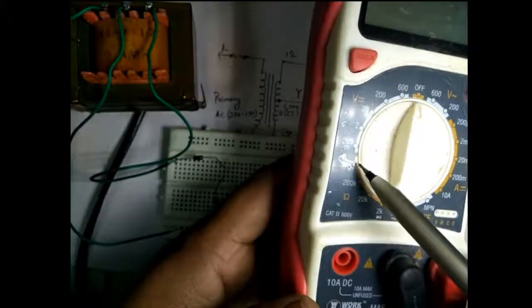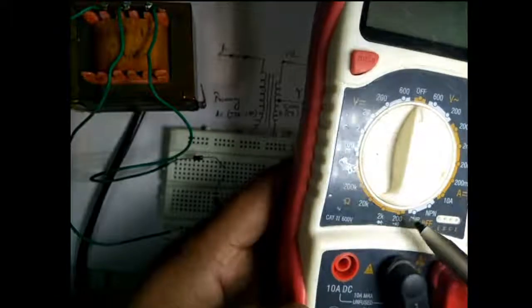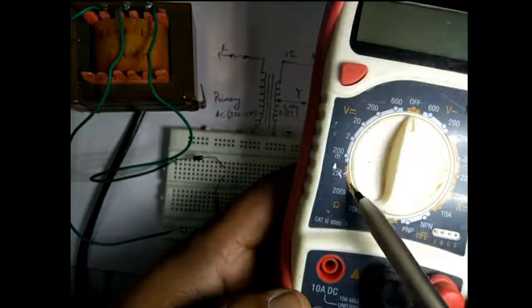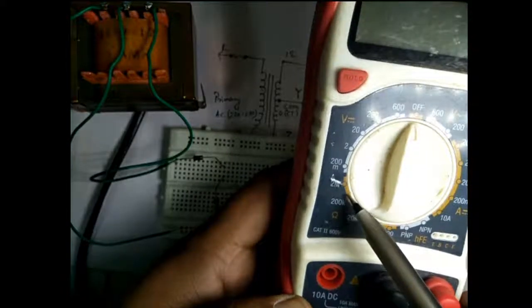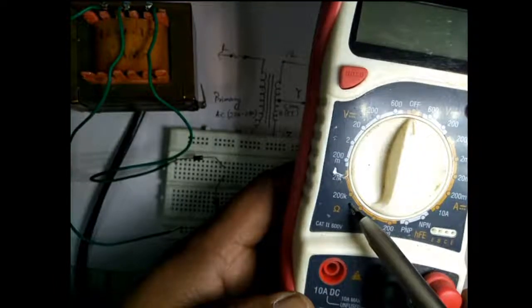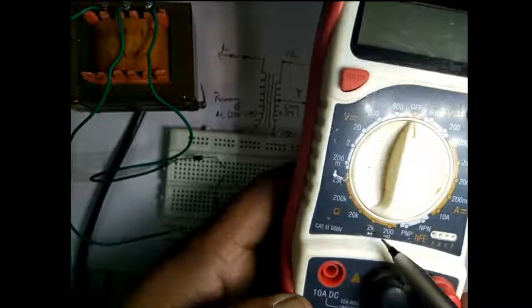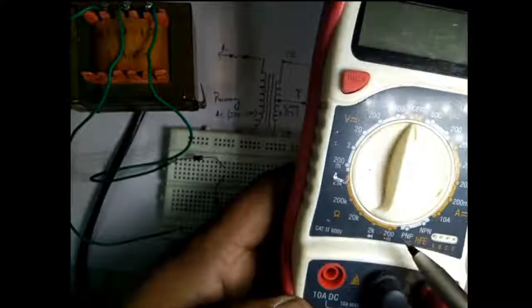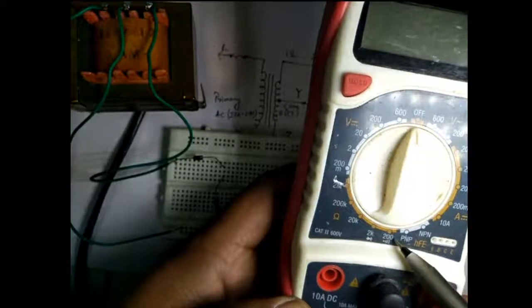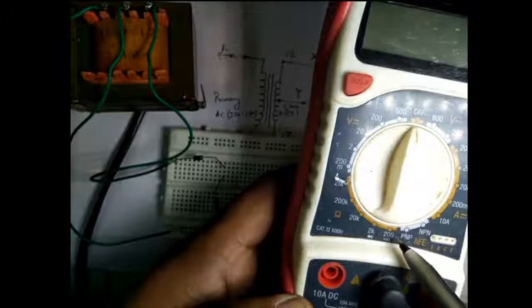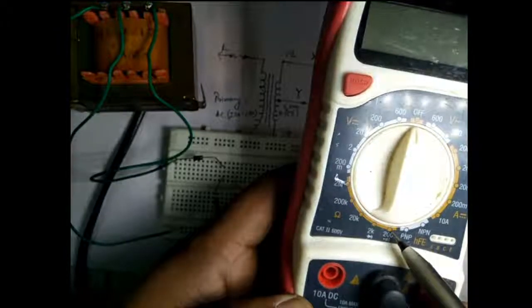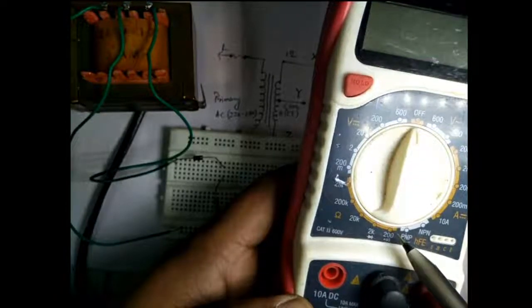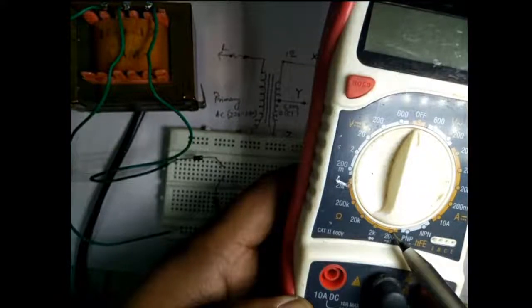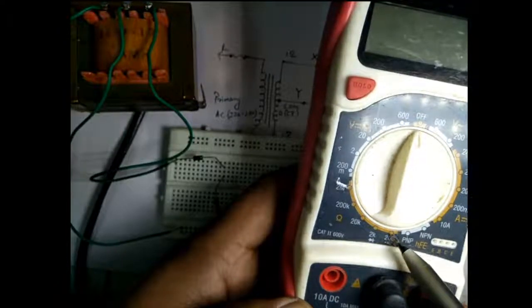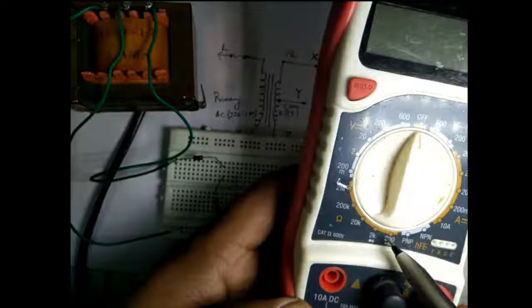Now, if we look into this side of the dial, what we can see is it's written 2 meg to M, 200K, 20K, 2K, 200. This means in this particular range, it is between 0 to 200 ohms. So any resistance value which is within this range can be measured, and similarly for other ranges.